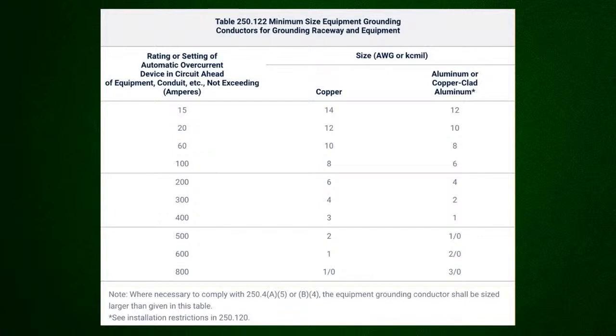If you look at this, so far up to this point, it says when I'm sizing these equipment grounding conductors that are going in these parallel runs here, it tells me to use table 250.122, except when I'm looking at a multi-conductor cable, then I have to make sure the circular mil exceeds. That's it. And why is that? Because a lot of times in cables you have a smaller type of equipment grounding conductor, and they want to make sure the circular mills in all those cables are enough to take care of that. Okay? That's why they're having you do that. All right? Now let's listen to a second part here.